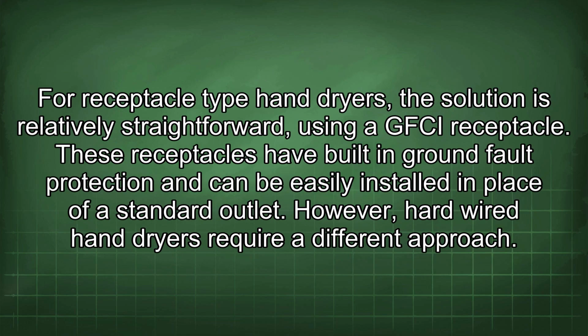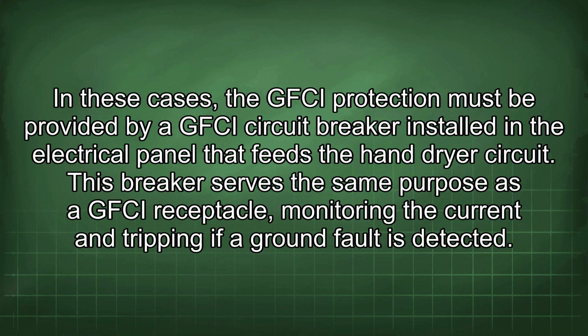For receptacle-type hand dryers, the solution is relatively straightforward, using a GFCI receptacle. These receptacles have built-in ground fault protection and can be easily installed in place of a standard outlet. However, hardwired hand dryers require a different approach. In these cases, the GFCI protection must be provided by a GFCI circuit breaker installed in the electrical panel that feeds the hand dryer circuit. This breaker serves the same purpose as a GFCI receptacle, monitoring the current and tripping if a ground fault is detected.